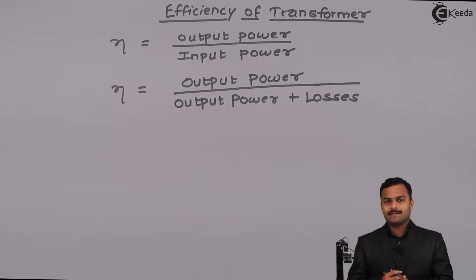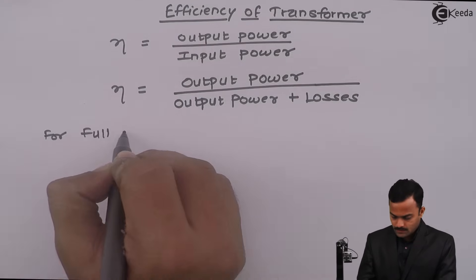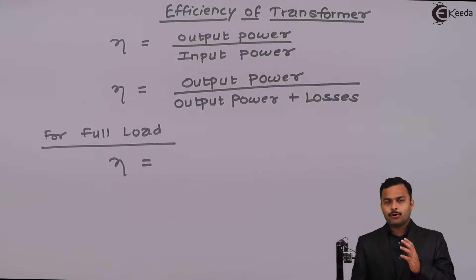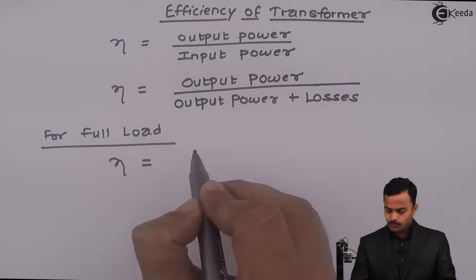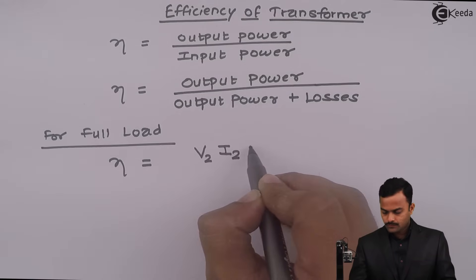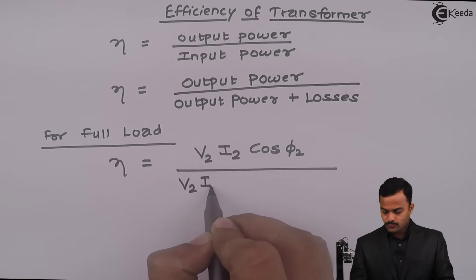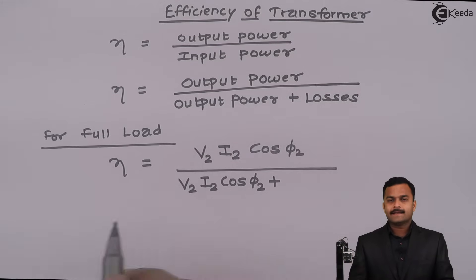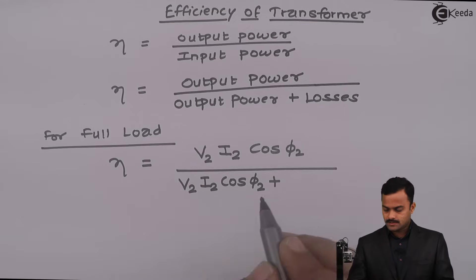The transformer rating is apparent power, so to get actual power I need to multiply it with power factor. For full load, efficiency equals output power at the secondary side, where a load having power factor cos Phi 2 is applied with secondary voltage V2 and secondary full load current I2. There are two losses in a transformer: core losses, also called iron losses, and copper losses.